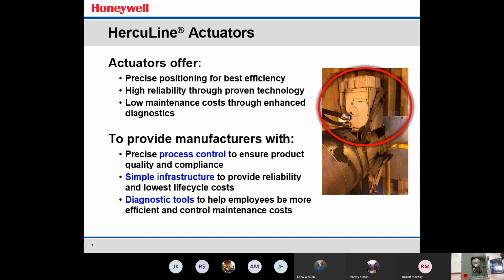Say, for example, your controller's changing from 4 milliamps to 4.002. You're going to see that actuator move, because at 1,000 repositions, you get a much more finite control out of your 4 to 20 milliamp signal. The same thing with the Herculine 2000. That offers upwards of about 500 repositions. So both of these actuators are going to take a very, very small bump in control signal to have a movement in that actuator. That's going to give you very, very good process control. It's going to save, hopefully, energy cost, maintenance cost, and provide a little bit better quality control on the product that they're manufacturing.